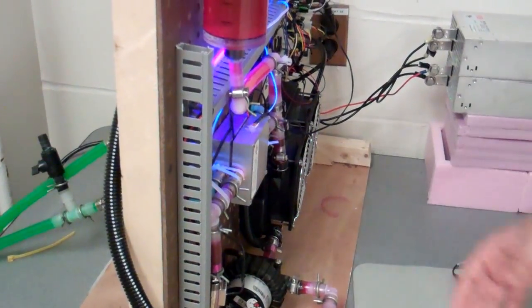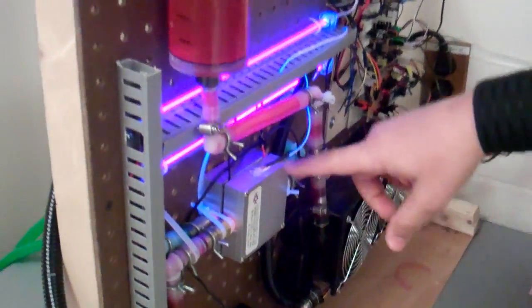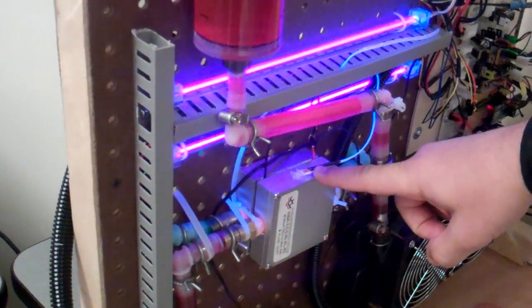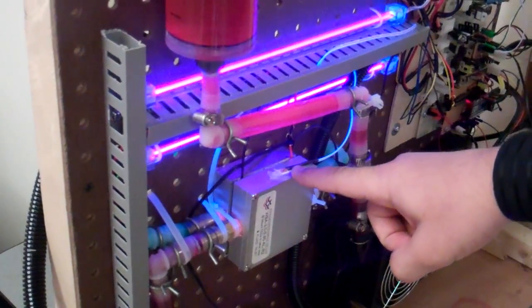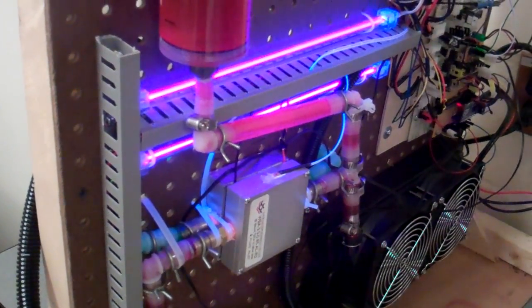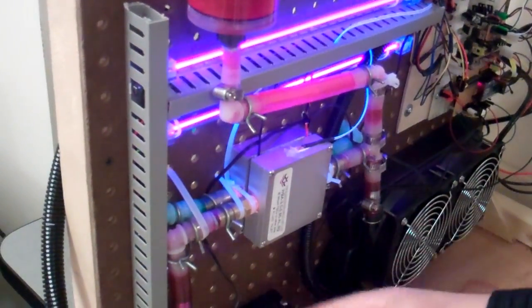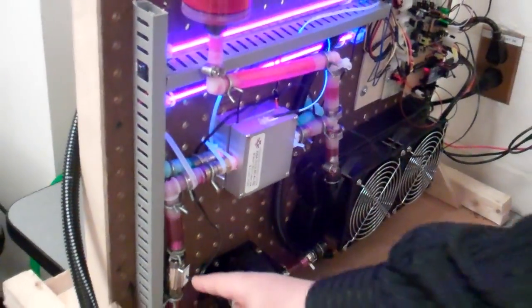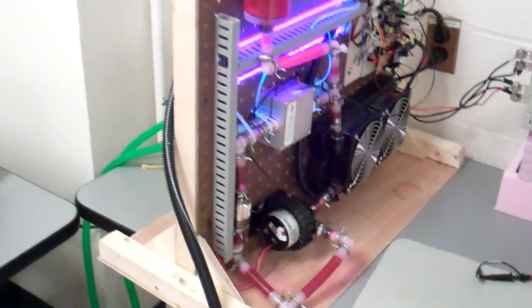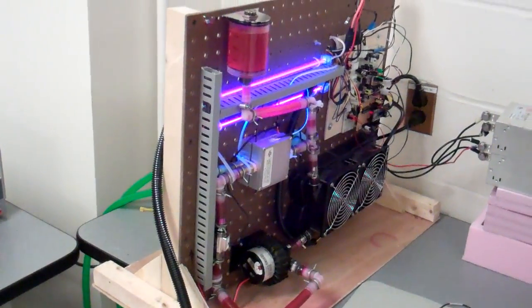We made some multiple checks for safety, so we're checking the temperature of the Peltier heater here. If it exceeds a certain temperature, then we will switch it off for safety. If there is no fluid running in the system, then we'll switch off the pump if there is any leakage or something.